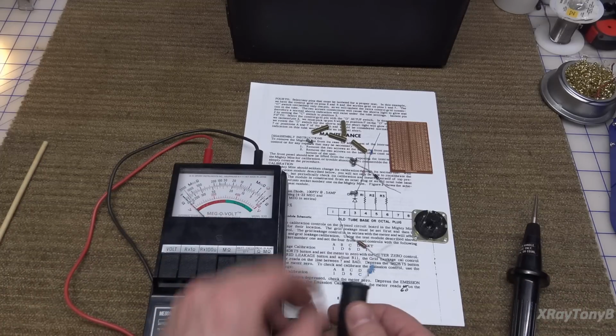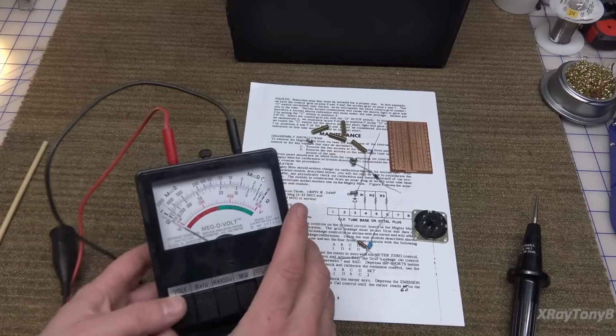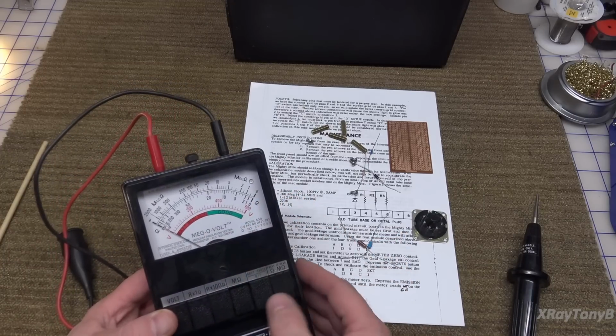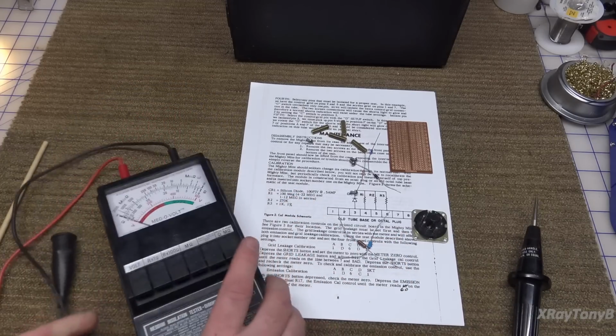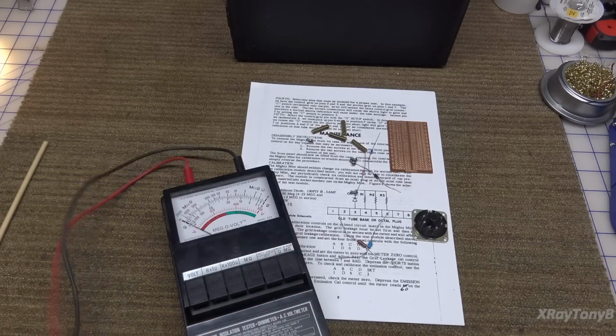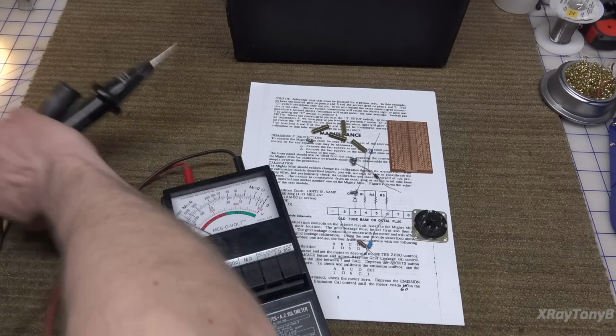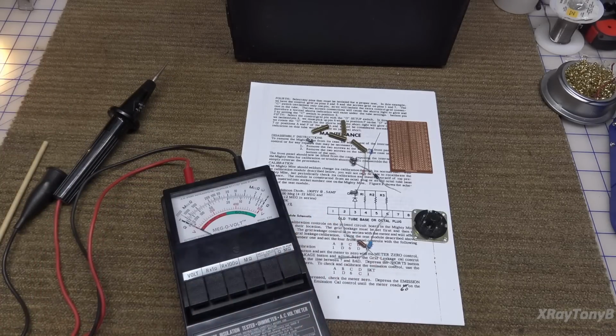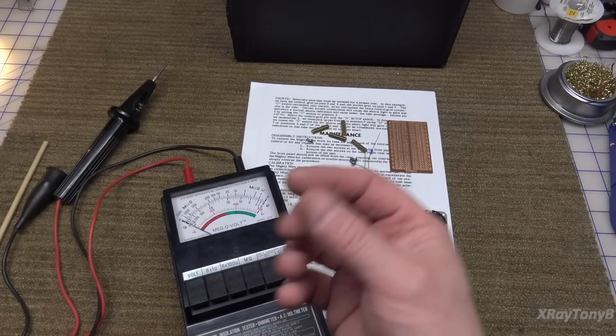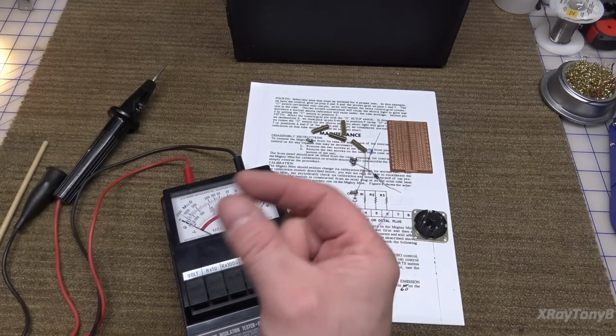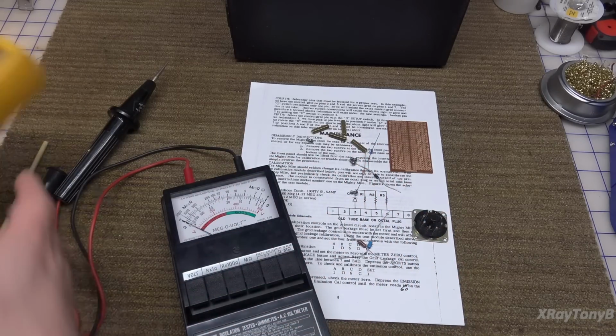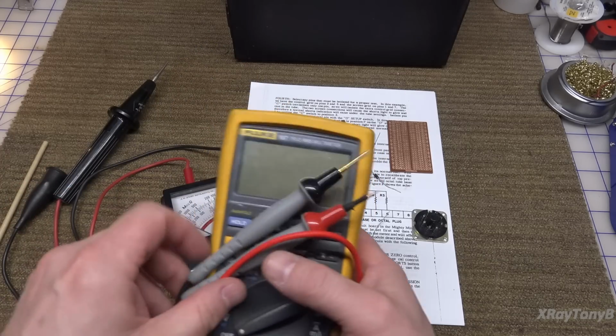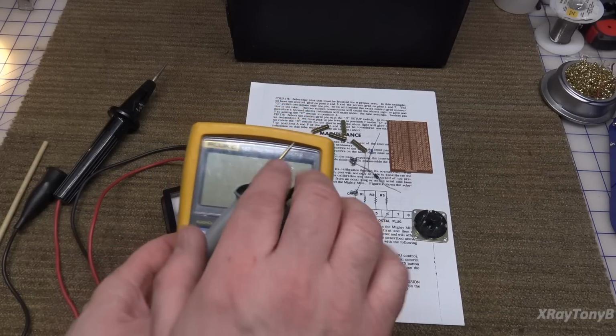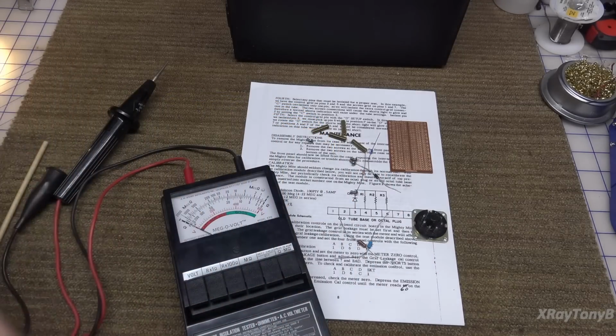So pretty cool. But some of these will actually go up to even 5 or even 10,000 volts test voltage, and we use these at work for testing high tension cables for X-ray machines, because they're rated up to about 80 kilovolts that they can withstand before the insulation will break down. But sometimes the core of the cable will break down and arc internally, and you'll get these little carbon tracks. And even though these meters here will read very high resistances, as you just saw, there's no real high voltage here, and it won't break it down sometimes. But this, when you use it, it will.